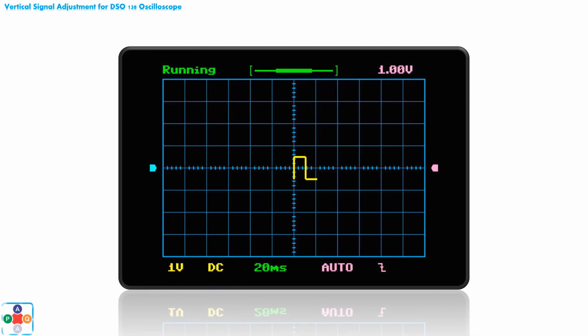If we introduce a signal with a peak-to-peak value of 1 volt, you guessed correctly, it will fit in 1 square by height. However, if we have previously centered our signal line to the exact middle of the screen, our signal will most likely, in absence of any DC offset, be centered on the display as well, so it will occupy 1/2 of the upper square, and 1/2 of the lower square, in regard to the centerline on the display. You will also notice that the top right icon on the display also shows the peak-to-peak value of our signal, in this case 1 volt.